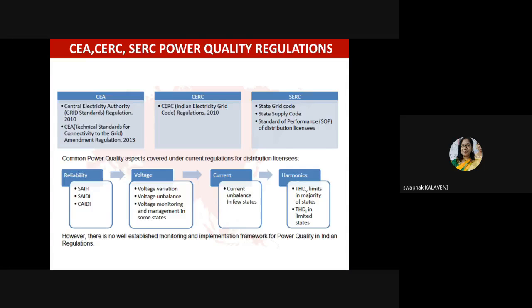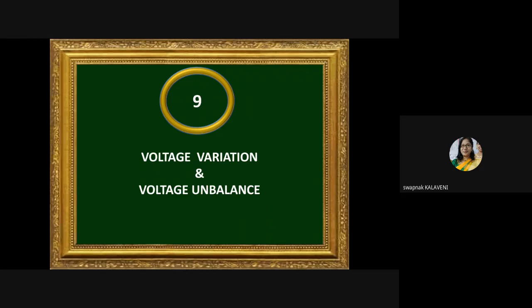Now we are giving special focus to voltage variation and voltage unbalance, because these two parameters are very important from the point of view of power quality, next to harmonics. So far we have discussed harmonics and their limits, and what is fixed in different states. The next element is voltage variation. How much is permitted? Say our voltage is 230 volts. Is it permitted to go beyond 230 volts? Shall it go to 300 volts? If it is less than 100 volts, what will happen? Voltage unbalance: if you are driving three-phase power, one phase voltage is 230, another phase voltage is 160, and the other phase voltage is 185. Is it allowed? We should understand what we have to do about those things.